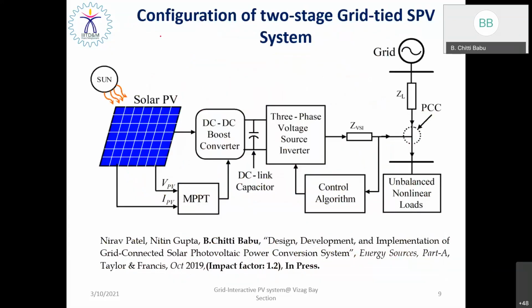This is the two-stage grid-tied solar PV system. Most researchers use a two-stage grid-tied solar PV system for good power flow between the solar PV and the utility grid. Two-stage means it has a DC to DC converter and a three-phase PWM voltage source inverter. In between there is DC decoupling, what is called a DC link capacitor, as it provides decoupling of the DC component.